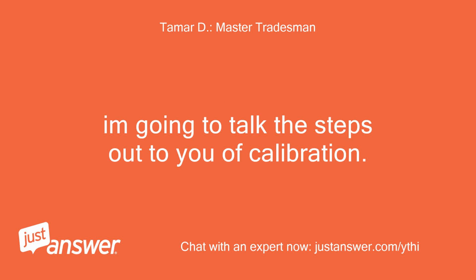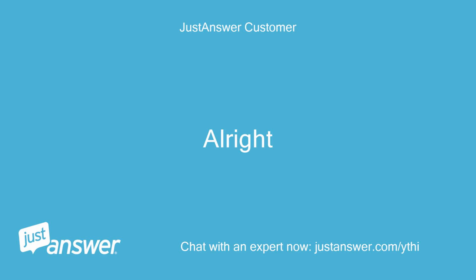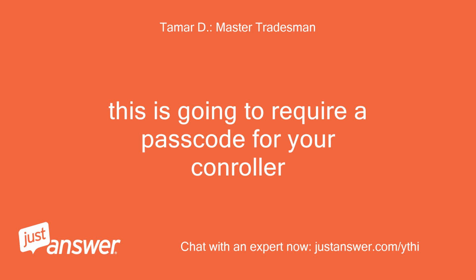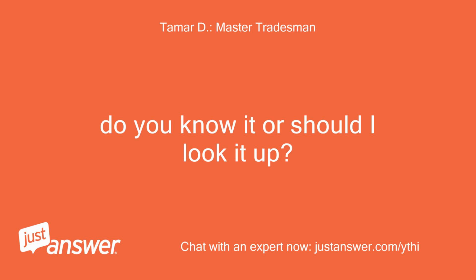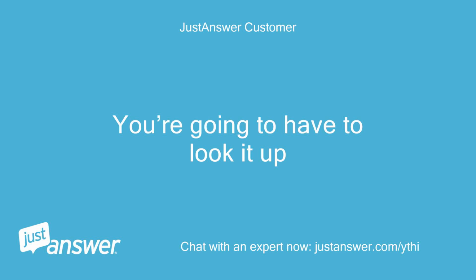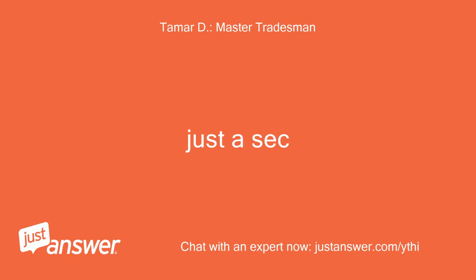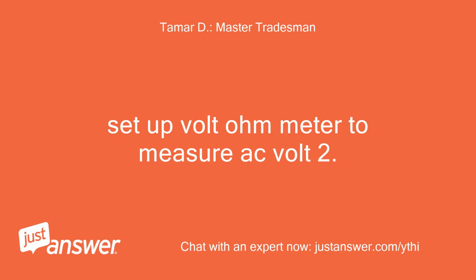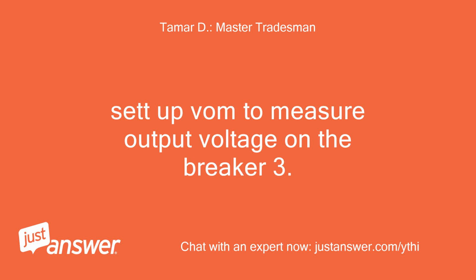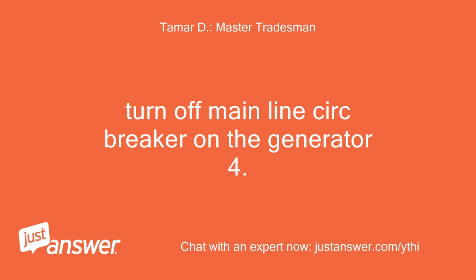I'm going to talk the steps of calibration out to you. All right. This is going to require a passcode for your controller. Do you know it or should I look it up? You're going to have to look it up. Just a second. 1. Set up the volt-ohm meter to measure AC volts. 2. Set it up to measure output voltage on the breaker. 3. Turn off the main line circuit breaker on the generator.